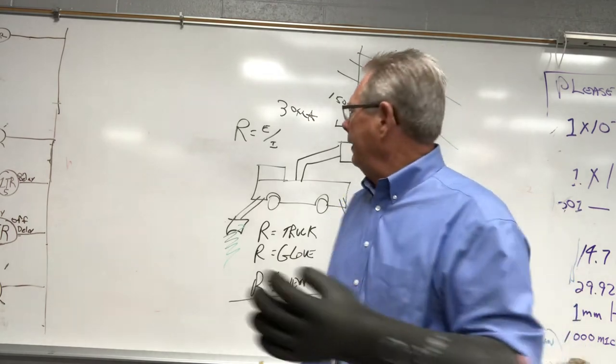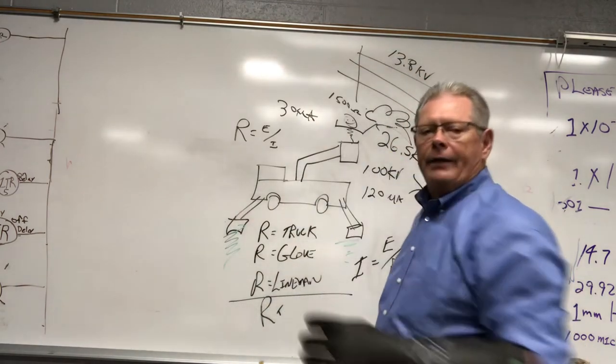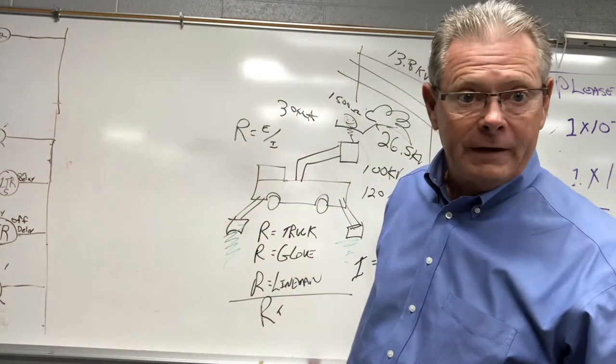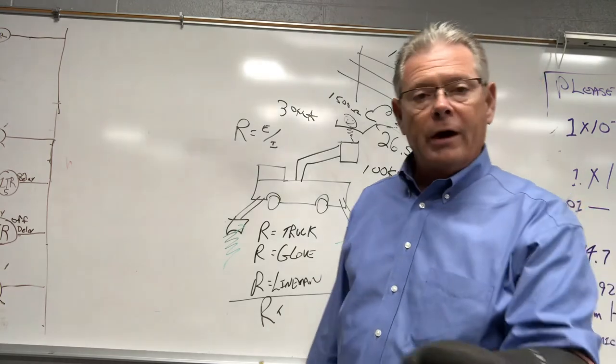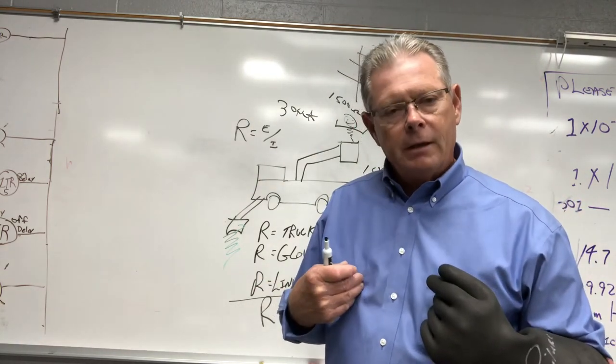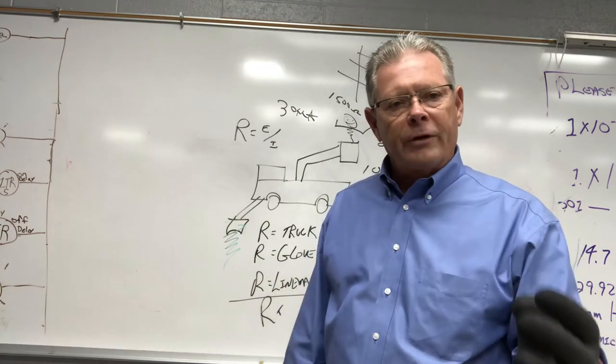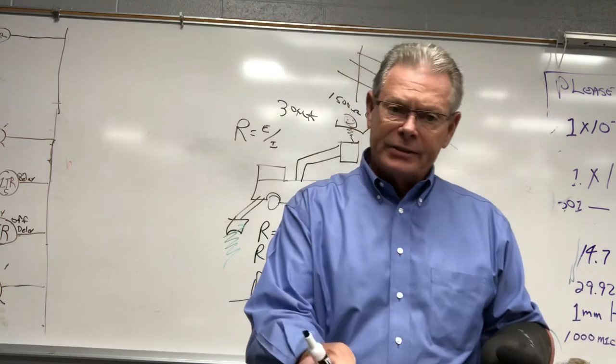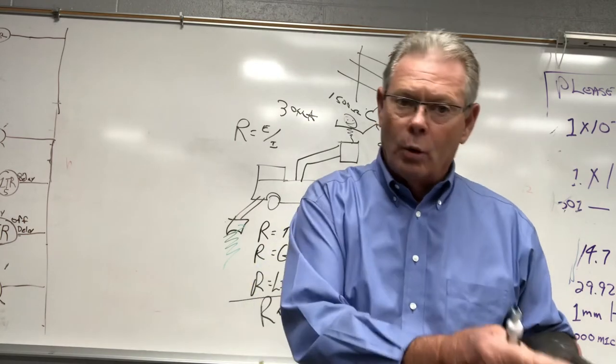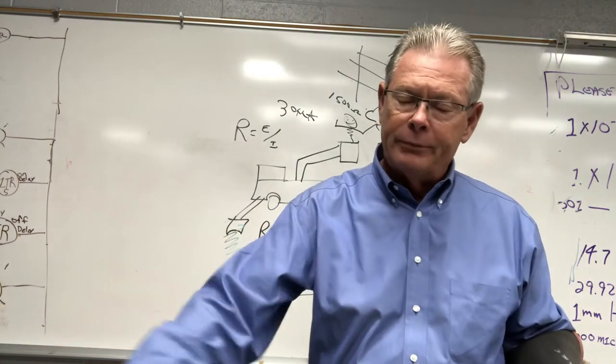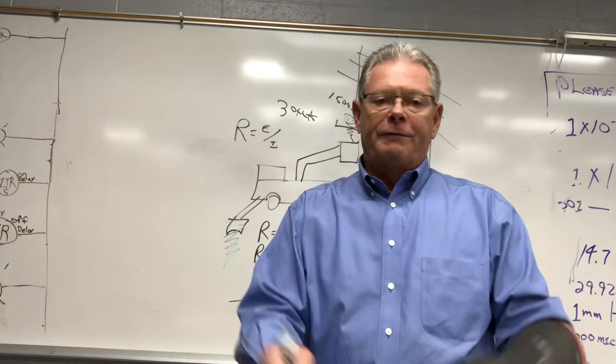So if that lineman's got gloves on and they're touching that line and there's current flowing, why don't they feel it? Well, a few hundred microamps is below the point of sensation. It takes one to three milliamps, or one to three thousandths of an amp, which is way more than just a few hundred microamps for us to feel it.